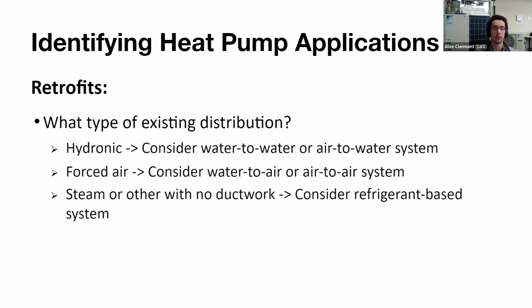We did see a question about whether some of these types of ductwork would have to be resized if you're trying to retrofit an existing building. I don't know if you answered that, Mike. Actually, it depends a little bit on what kind of building you're looking at, but we've seen applications where a gas-fired unit was doing the whole heating for the whole building, and we actually retrofitted that existing air handler and used all the existing ductwork. Essentially, it's now a fully air source machine. It's still an air handler, but it's using a coil tied to an air source heat pump machine on the roof. And essentially, it cools and heats the whole building, and it uses all the existing ductwork. So it does depend a little bit on what kind of building we're looking at, because sometimes it is possible to do that.